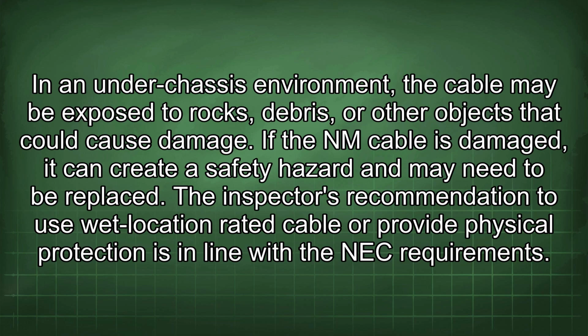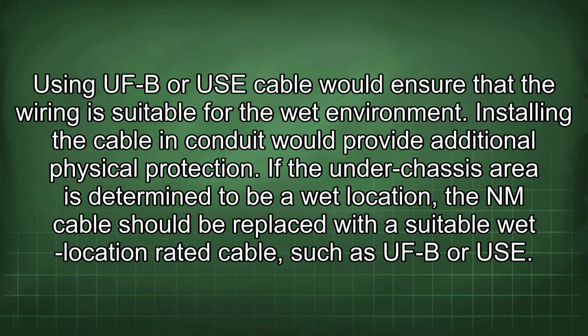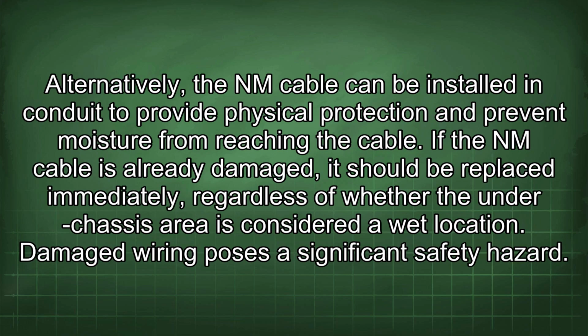The inspector's recommendation to use wet location rated cable or provide physical protection is in line with the NEC requirements. Using UFB or USE cable would ensure that the wiring is suitable for the wet environment. Installing the cable in conduit would provide additional physical protection. If the under-chassis area is determined to be a wet location, the NM cable should be replaced with a suitable wet location rated cable, such as UFB or USE. Alternatively, the NM cable can be installed in conduit to provide physical protection and prevent moisture from reaching the cable.